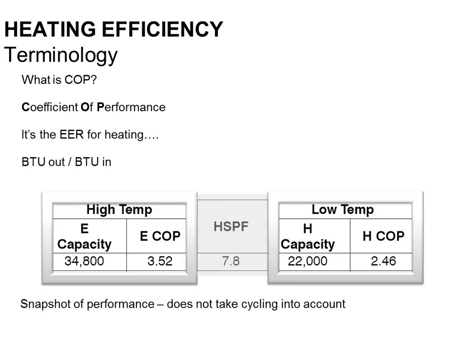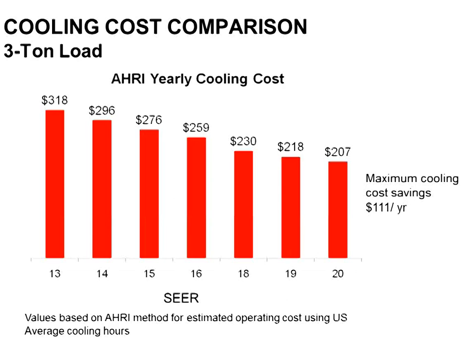If I look at different SEER ratings on the cooling side, like I said, people like to focus on SEER. It sounds exciting and everything. This is a national average, right? So if I put in a 20 SEER, which is kind of like a top-of-the-line air conditioner, and actually this is a residential example, I should specify that, instead of a 13 SEER air conditioner, it's going to save me $100 for the whole year. National average, right? That's taking into account people in Florida and Alabama that use a lot of cooling. So when we look at Chicago and Northwest Indiana and Wisconsin and Minnesota, it's even less for us. We don't save that much energy by putting in the most efficient air conditioner in the world, right?